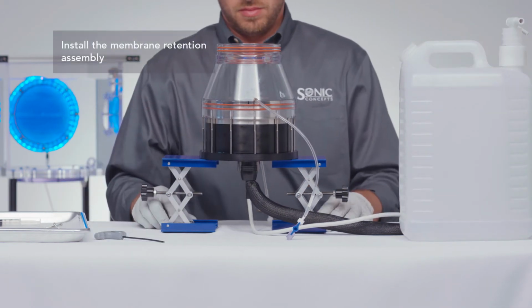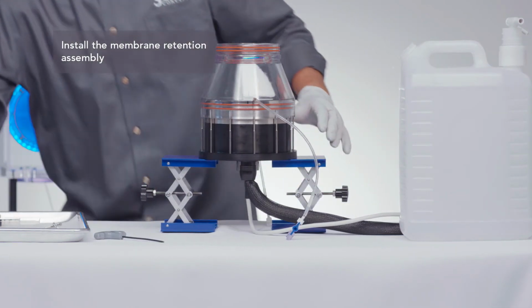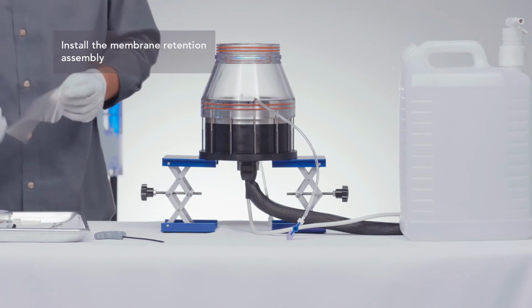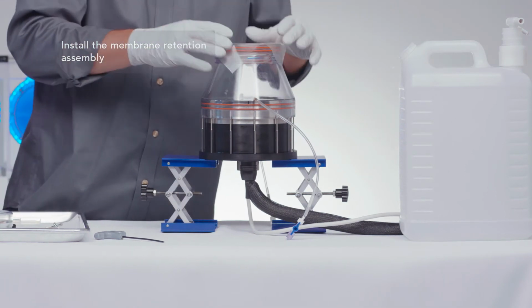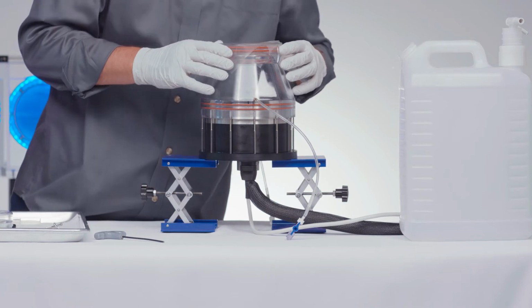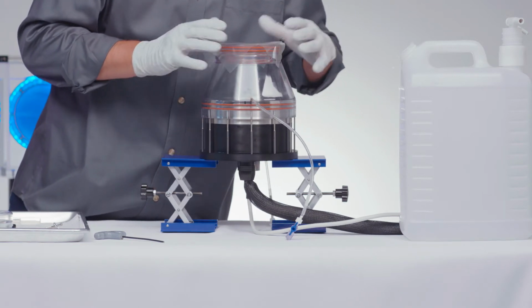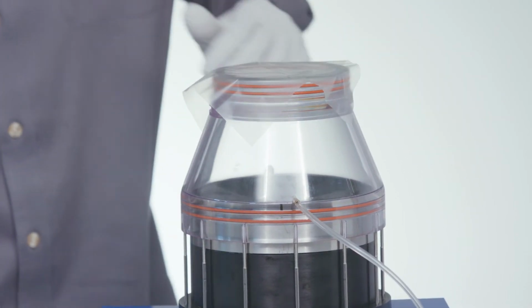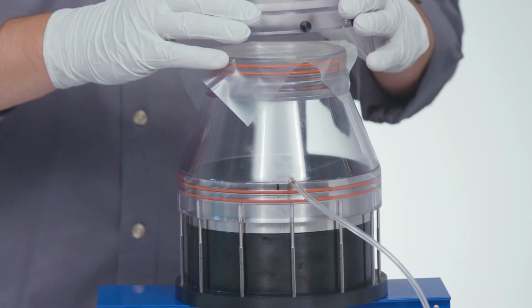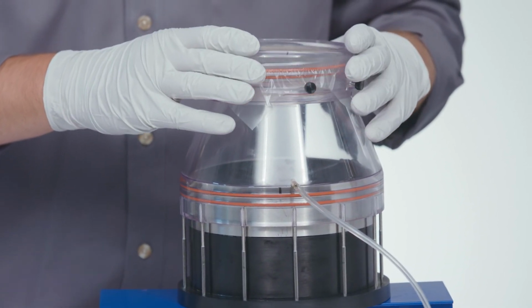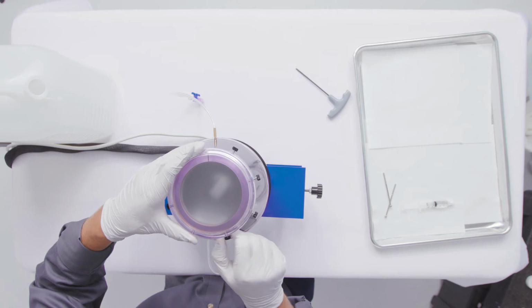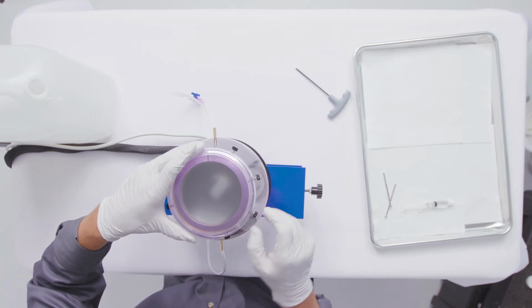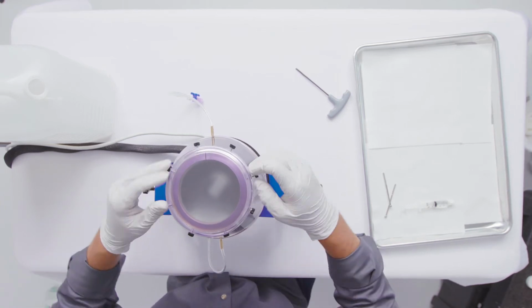Use appropriate fixturing to hold the transducer with its spherical surface facing upwards. Allow for enough distance for a 4-inch bend relief in the cable. Center the membrane with respect to the coupling cone's opening. Push the membrane retention ring over the membrane until it bottoms out to the cone. This mechanism should stretch the membrane material to a drum-like surface. Engage all 8 thumb screws to retain the assembly.